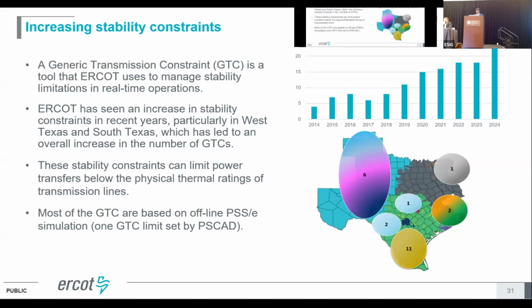When we identify any instability issue, we create an interface for that pocket called a GTC, or generic transmission constraint. We try to determine the safe or secure limit that can transfer flow across that interface without causing stability concerns, and then use those limits to manage the flow below that level across those stability-constrained areas.